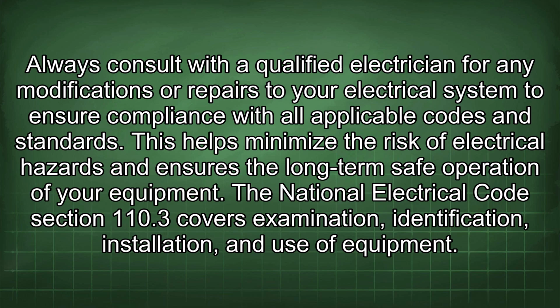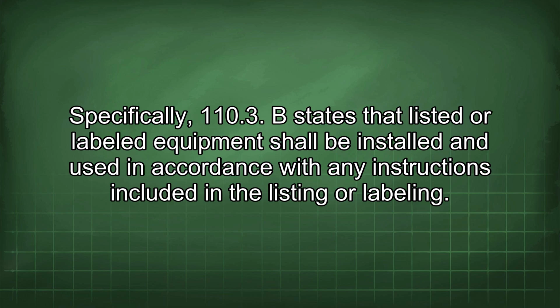The National Electrical Code Section 110.3 covers examination, identification, installation, and use of equipment. Specifically, 110.3(B) states that listed or labeled equipment shall be installed and used in accordance with any instructions included in the listing or labeling.